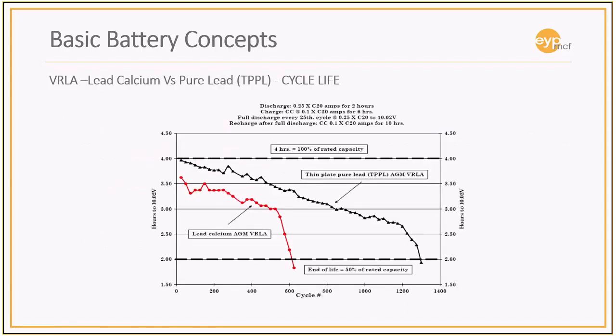In this chart, we're looking at the standard valve regulated lead calcium battery versus the pure lead battery, comparing cycle life. The pure lead battery is built for a lot more cycles than your typical AGM valve regulated battery. As you increase the cycles, life drops off on the typical AGM valve regulated battery, but for the pure lead battery, doing quite a few cycles doesn't kill the battery that quickly, and it goes out to several more cycles. So one of the other benefits of the thin plate battery is that you can cycle it more.